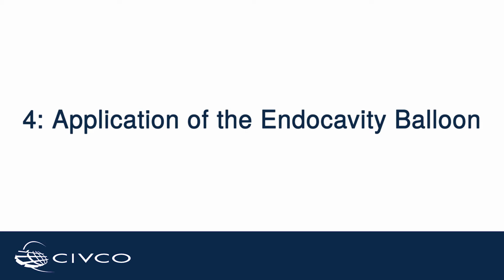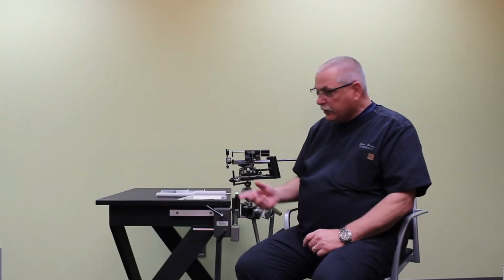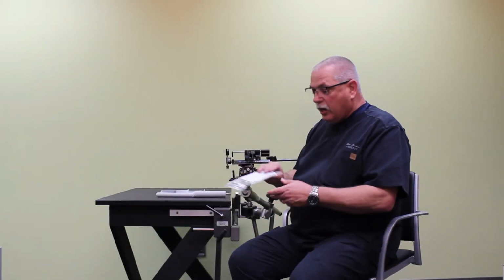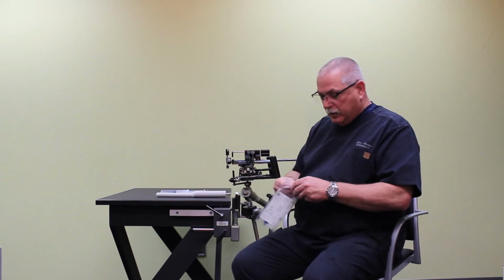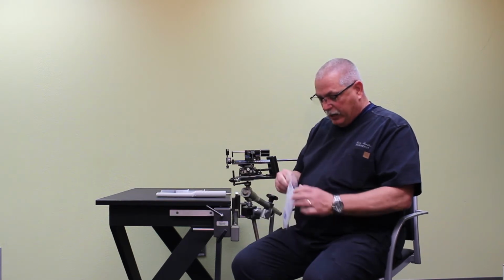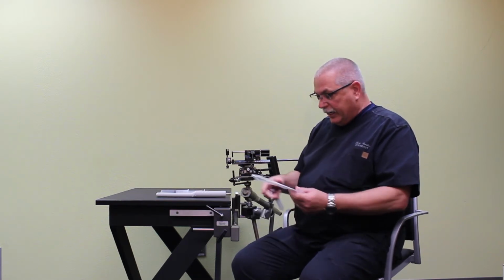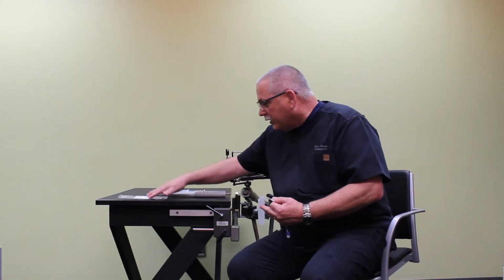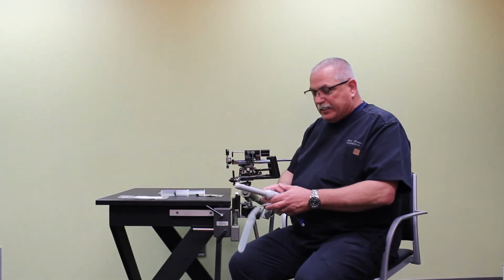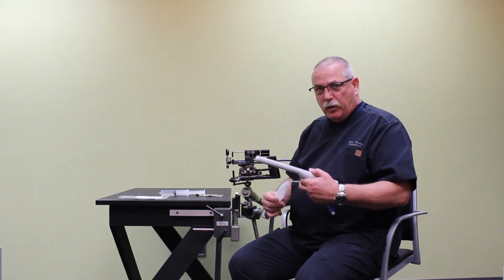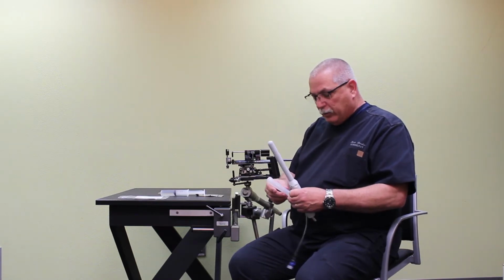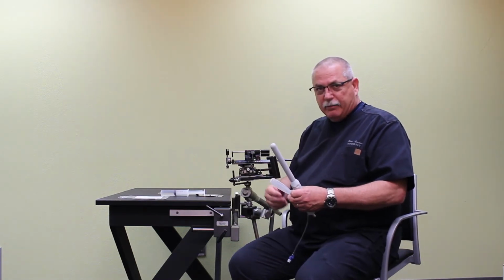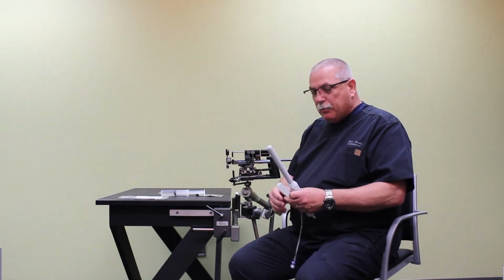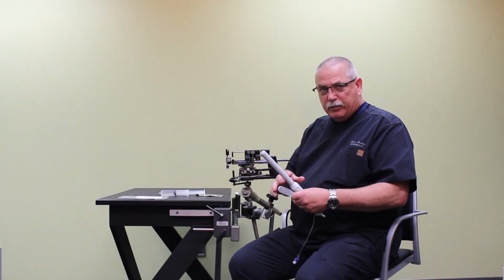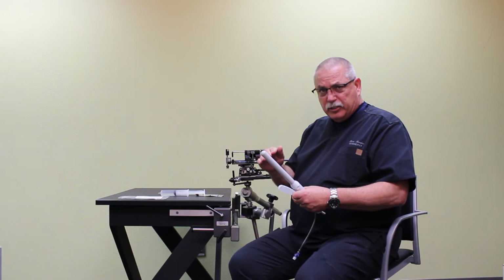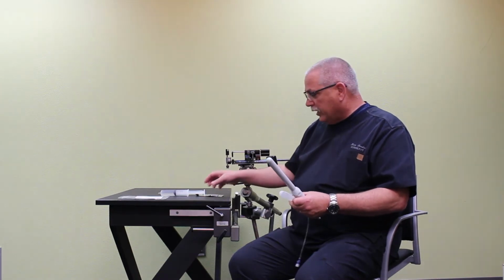Next, we'll place the endocavity balloon onto the probe itself. So we'll take the balloon out of its case, and it's important to note that the endocavity balloon, its main purpose is to position the prostate. Now, with the fluid around the prostate during imaging, that may in fact improve the image, but the number one reason for using the endocavity balloon is to be able to position the prostate properly there on the ultrasound screen.